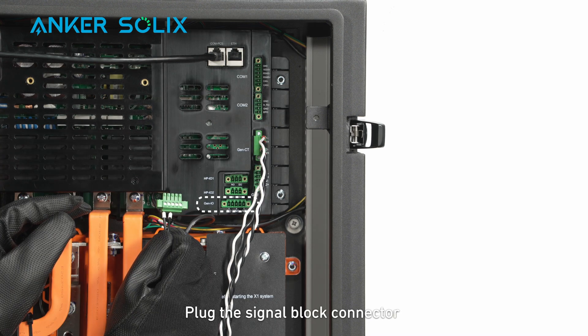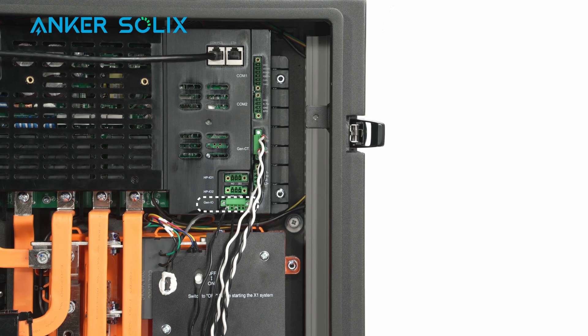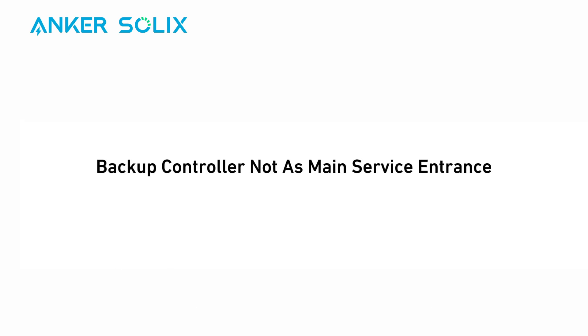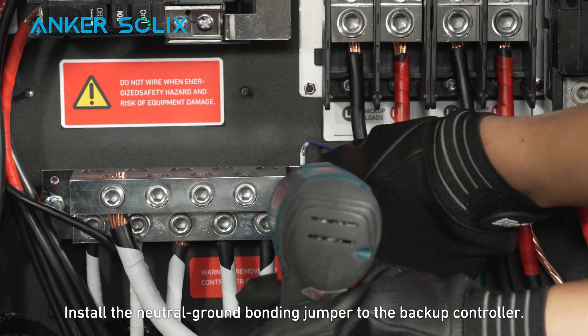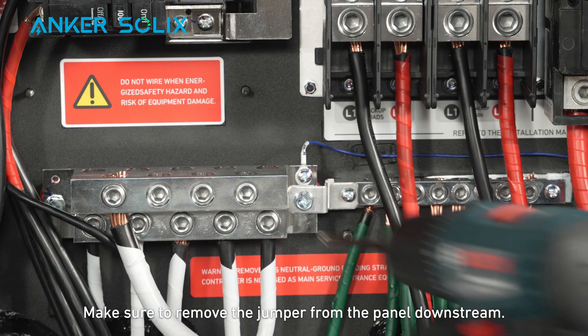Plug the signal block connector into the terminal block socket labeled Gen-I/O. If you want to make other communication wiring for the backup controller, you need to insert the signal cables into an appropriate terminal block connector and plug it into the terminal block socket. Install the neutral ground bonding jumper to the backup controller. Make sure to remove the jumper from the panel downstream.